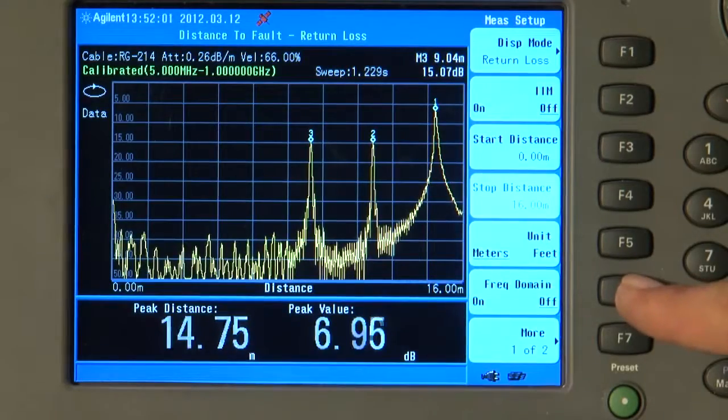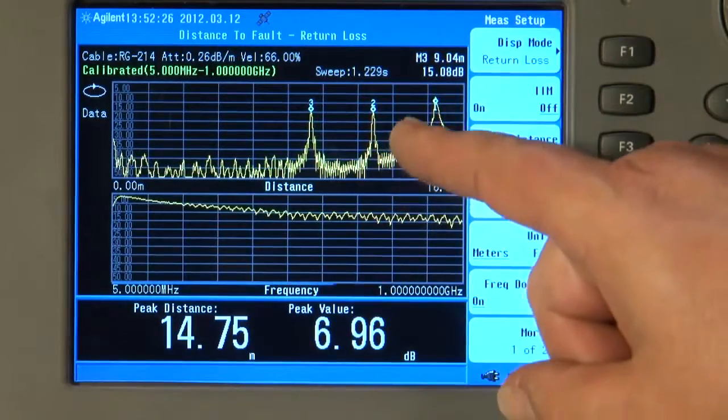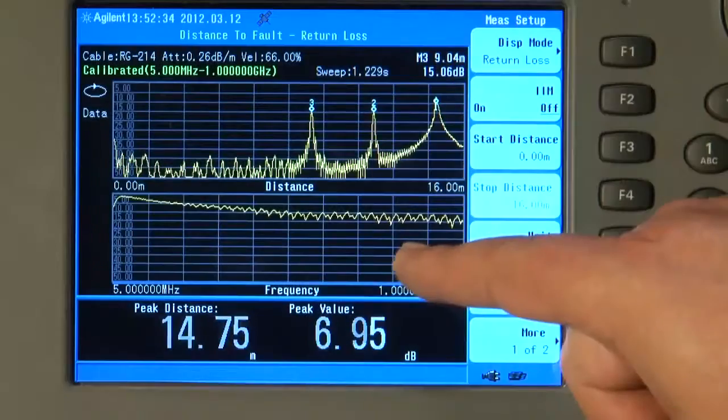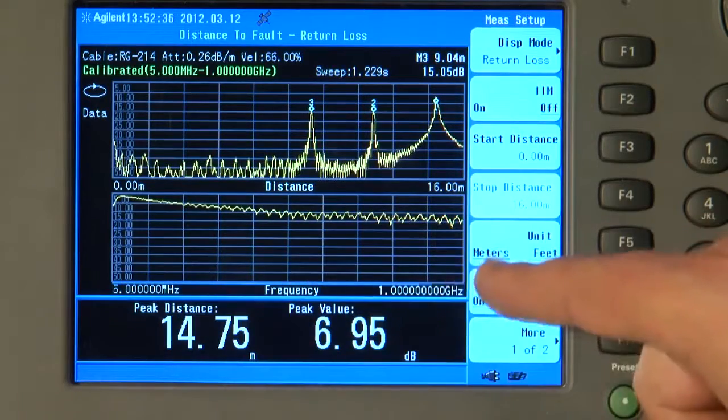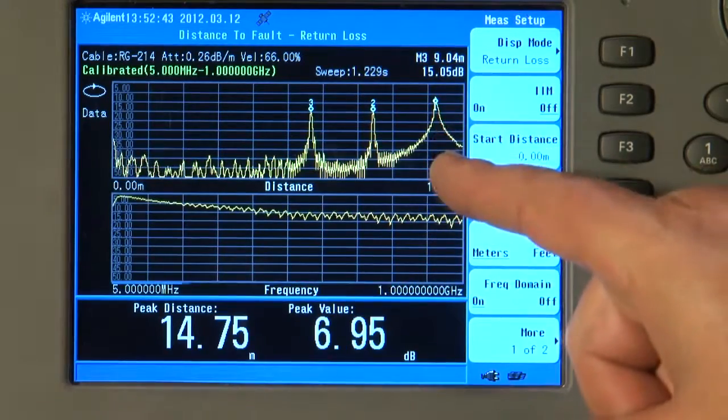And there is one more really nice feature of the distance to fault measurement on the HSA. You will see here there is a button called Frequency Domain. If I turn that on, now the screen is split into two displays. The top half is still showing us return loss versus distance, the same distance to fault measurement we were making just now. But now the lower half of the screen is showing us return loss versus frequency. So we can make a normal return loss measurement at the same time as making a distance to fault measurement.